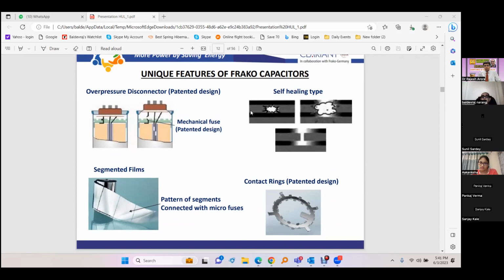MPP capacitors are the latest development. They have self-protection and self-healing. Whenever there is a high inrush current for any reason, the metallization on the film evaporates, the fault is cleared, and the system remains in service without isolation. Then there is an overpressure interrupter mechanism. If the faults are very heavy and there is a lot of gas formation, the overpressure lifts the lid, the connection is mechanically broken, and the system is taken out of service.